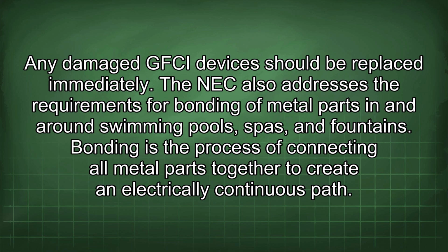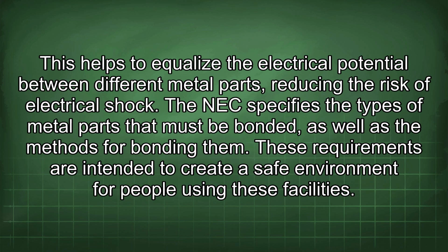The NEC also addresses the requirements for bonding of metal parts in and around swimming pools, spas, and fountains. Bonding is the process of connecting all metal parts together to create an electrically continuous path. This helps to equalize the electrical potential between different metal parts, reducing the risk of electrical shock. The NEC specifies the types of metal parts that must be bonded, as well as the methods for bonding them. These requirements are intended to create a safe environment for people using these facilities.